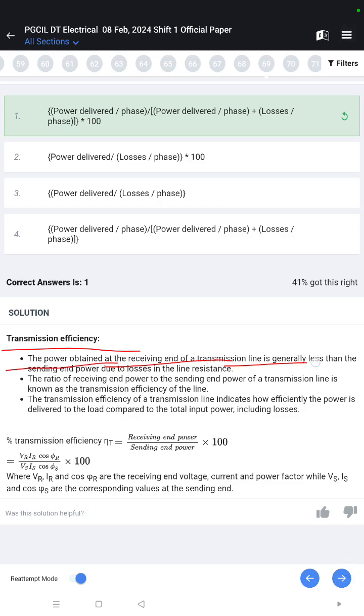Transmission efficiency: the power obtained at the receiving end of a transmission line is generally less than the sending end power due to losses in the line resistance. The ratio of receiving end power to the sending end power of a transmission line is known as the transmission efficiency of the line. It indicates how efficiently the power is delivered to the load compared to the input power including losses.